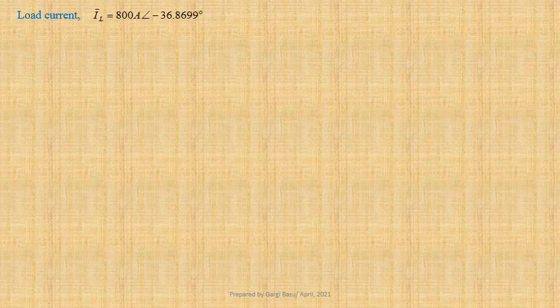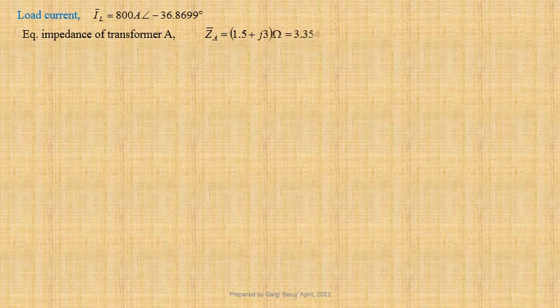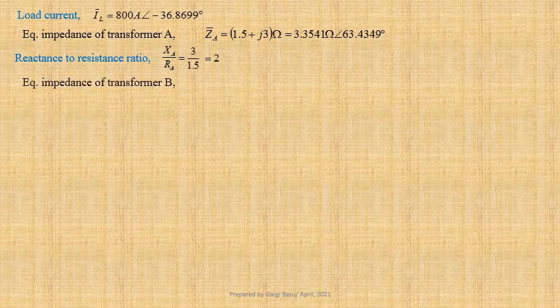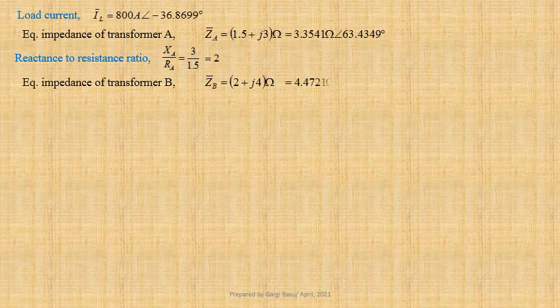Given load current IL equals 800 ampere at an angle minus 36.8699 degree. Equivalent impedance of transformer A, ZA equals 1.5 plus J3 ohm, that is equal to 3.3541 ohm at an angle 63.4349 degree. Reactance to resistance ratio XA by RA equals 3 by 1.5, that is equal to 2. Let us assume that equivalent impedance of transformer B, ZB equals 2 plus J4 ohm, that is equal to 4.4721 ohm at an angle 63.4349 degree.